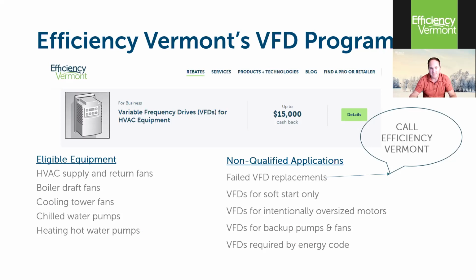Non-qualified applications, failed VFD, I put the bubble in here, call Efficiency Vermont. If we can make the legitimate case that this pump or fan could run across the line, the drive has failed. I had a compressor not long ago that had a drive on it. That compressor VFD failed. Now the compressor runs across the line. And it's been like that for 3 months. So that project, there's no code requirement or process requirement that says that replacement drive has to go in, so the lane is clear to help support the replacement drive in that application.